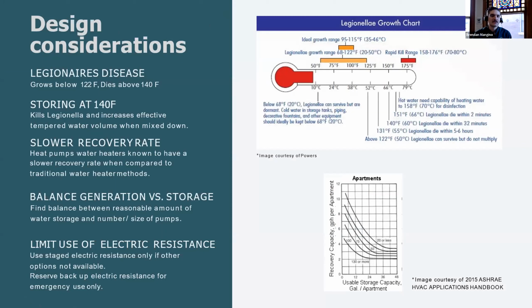Something I look at when I'm designing a central heat pump domestic hot water system is, first, Legionella. I'm always looking at this. Legionella typically thrives at the target tempered water temperature. So for most projects, and especially projects with people with compromised immune systems, younger children, or the elderly, I like to store water above that temperature. I also like to mix that down, because the same people that are at highest risk of Legionella are also at the highest risk of scalding. So I always store at 140 as my target temperature, and that'll kill off Legionella within 30 minutes.